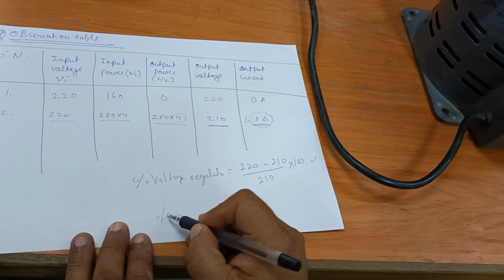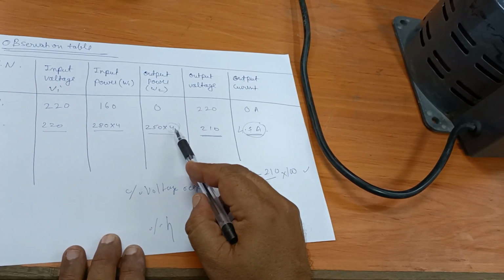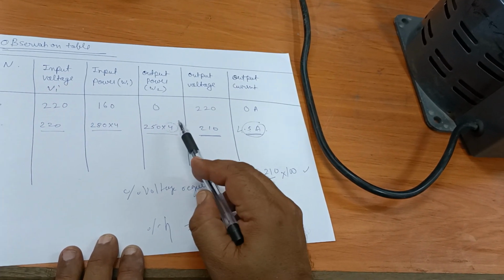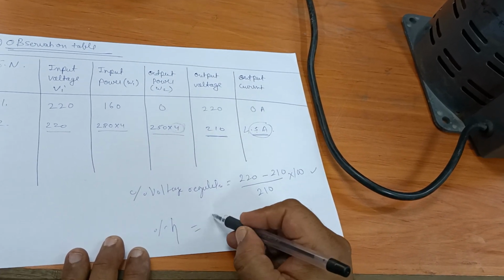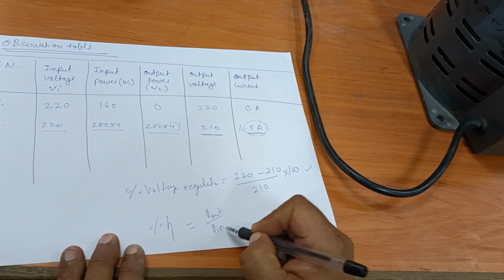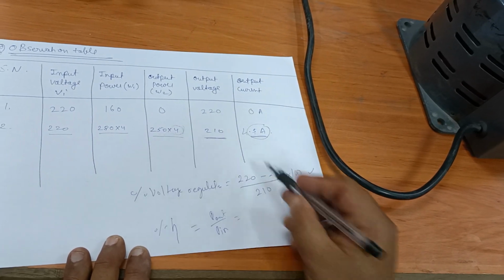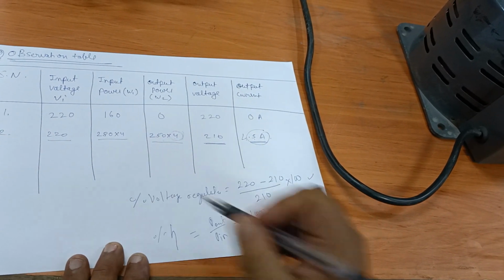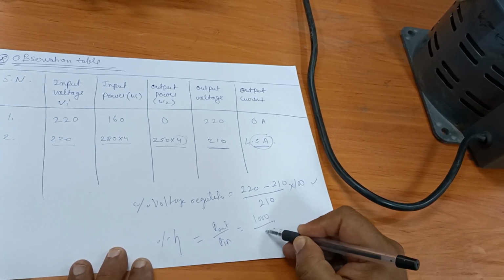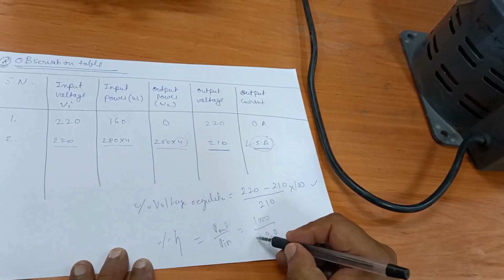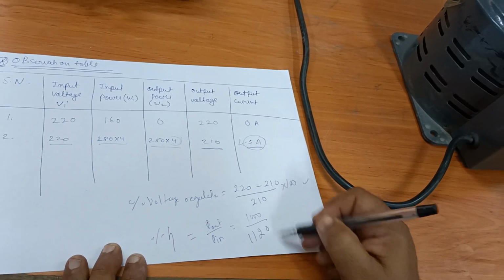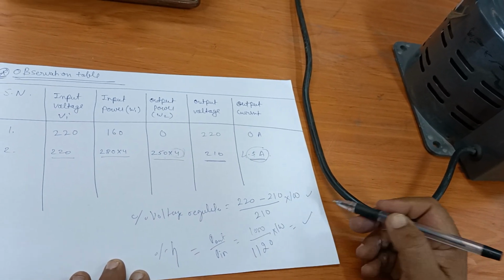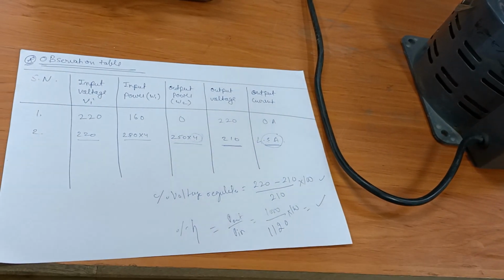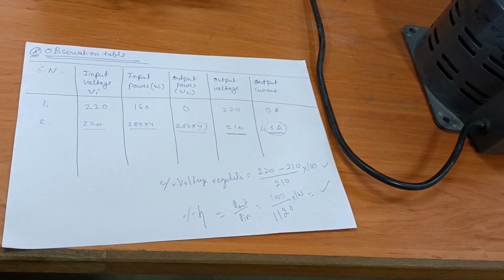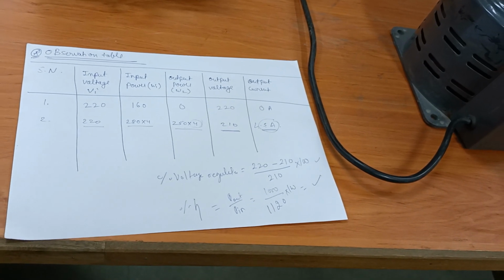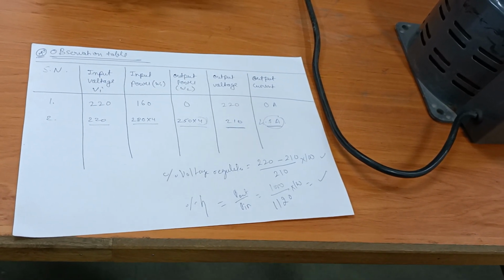Now come percentage efficiency. Percentage efficiency is again at full load condition, that is P out upon P in. P out is 250 into 4, that is 1000 watt, and P input is 1120. So you calculate this, multiply by 100, and you will get the percentage efficiency. You will be surprised to know that a transformer usually has efficiency between 98 to 99%, because the losses are very minimum since it is a static device.